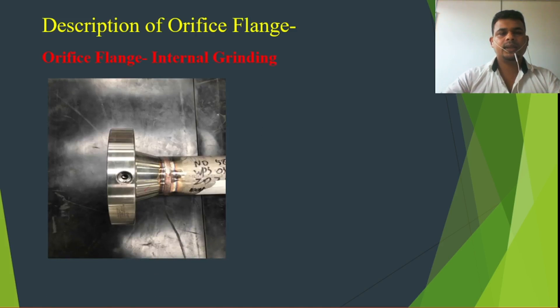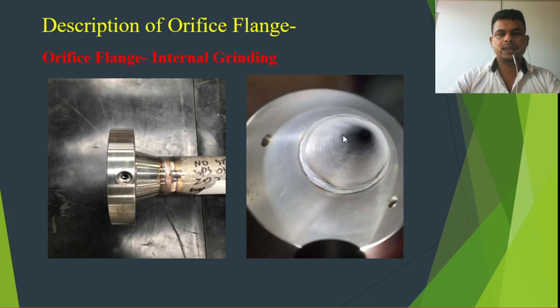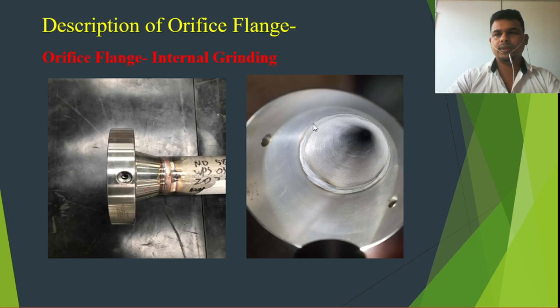Another important topic is orifice flange internal grinding. When we weld the orifice flange to the pipe, we know that weld root can protrude inside. If the root protrudes, it creates a disturbance during water or gas flow, affecting the orifice meter reading. So you cannot get a proper reading from the orifice meter. That is the purpose of grinding — I will show you.